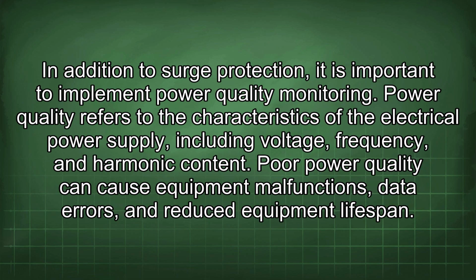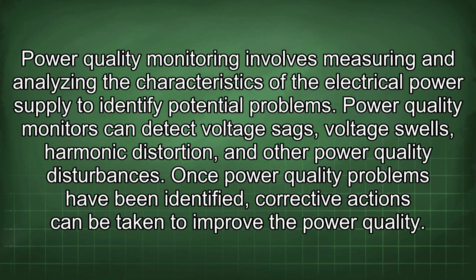In addition to surge protection, it is important to implement power quality monitoring. Power quality refers to the characteristics of the electrical power supply, including voltage, frequency, and harmonic content. Poor power quality can cause equipment malfunctions, data errors, and reduced equipment lifespan. Power quality monitoring involves measuring and analyzing the characteristics of the electrical power supply to identify potential problems. Power quality monitors can detect voltage sags, voltage swells, harmonic distortion, and other power quality disturbances.